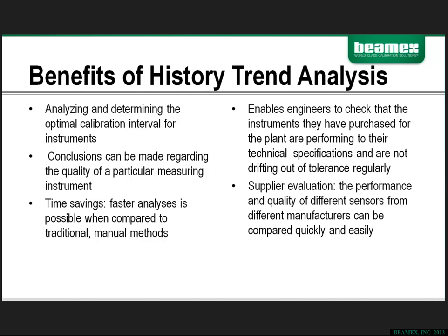History trend analysis is also going to verify instrument performance compared to the manufacturer specifications. So it's going to look at how this particular instrument performed as a whole based on the manufacturer's specs. And from that, you can determine whether it's primarily in tolerance, and if it's out of tolerance, whether that is significant. Significant is a term in calibration that defines when an instrument is out of tolerance by more than 1.5 times its manufacturer's specified tolerance.